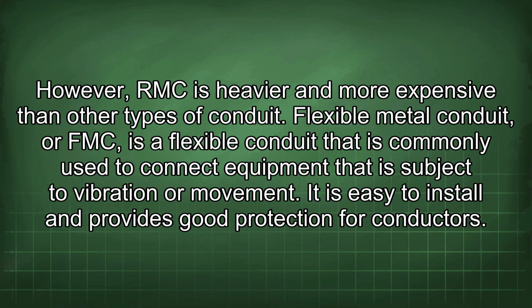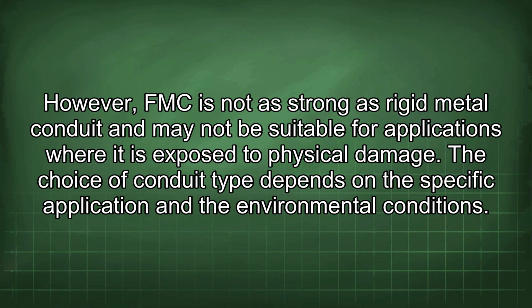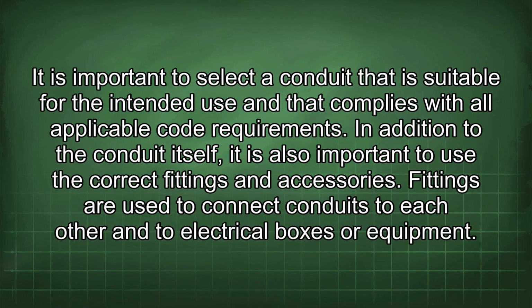Flexible metal conduit, or FMC, is a flexible conduit that is commonly used to connect equipment that is subject to vibration or movement. It is easy to install and provides good protection for conductors. However, FMC is not as strong as rigid metal conduit and may not be suitable for applications where it is exposed to physical damage. The choice of conduit type depends on the specific application and the environmental conditions. It is important to select the conduit that is suitable for the intended use and that complies with all applicable code requirements. In addition to the conduit itself, it is also important to use the correct fittings and accessories.